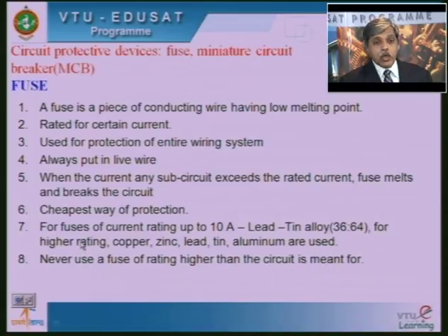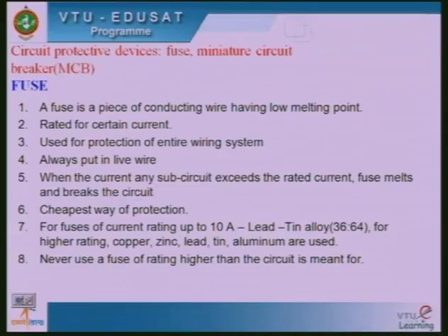As I told you, when the current rating of the entire circuit is 10 amperes, which means it cannot carry more than 10 amperes, I can put only a fuse of 10 amperes rating. If I put a 15 ampere fuse and the current drawn by the circuit is 12 amperes, larger than the rated current of 10 amperes, the fuse will not melt, but the equipment will be drawing larger current. Therefore there is a possibility of damage to the equipment because of excess current drawn by the system from the supply.